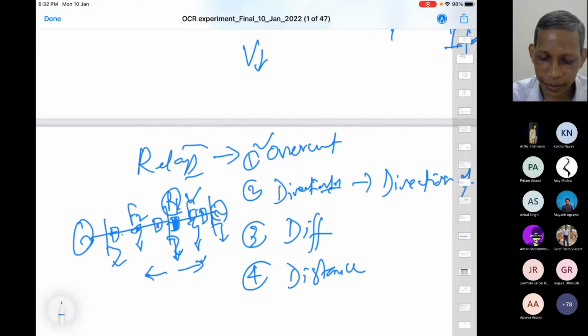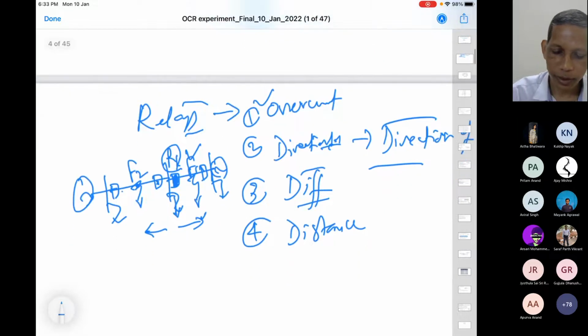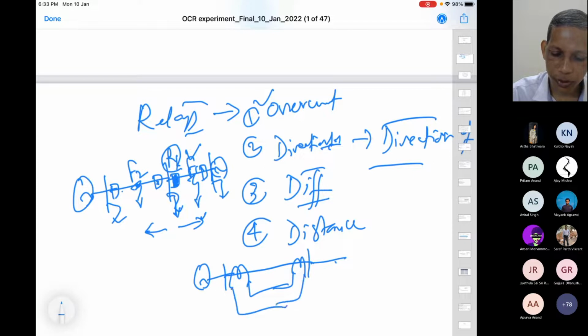So therefore, we require directional information, and directional information means information of the direction of the fault with respect to the relay or the measurement point. And that is what we talk about as directional information or directional relay. Then differential, current differential, and in one quick nutshell, I can elaborate with you. This is a current differential I can put for a line or transformer. So I'm putting it like this.